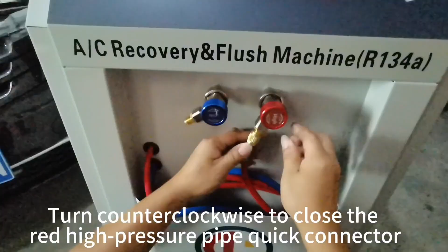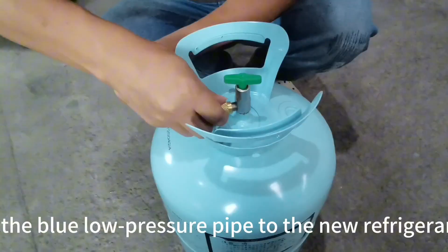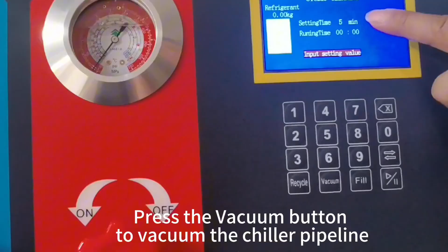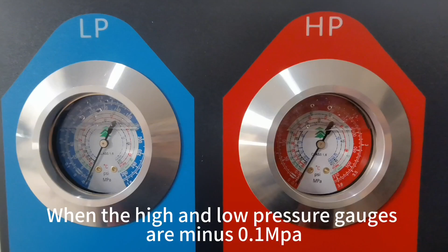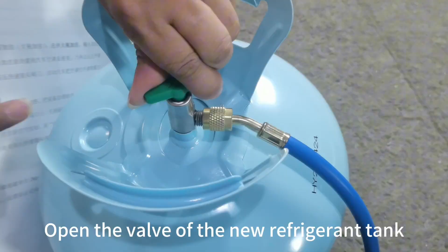Turn counterclockwise to close the red high pressure pipe quick connector. Connect the blue low pressure pipe to the new refrigerant tank. Open the HP valve and LP valve counterclockwise. Press the vacuum button to vacuum the chiller pipeline. When the high and low pressure gauges are -0.1 MPa, it means vacuuming is complete. Open the valve of the new refrigerant tank.